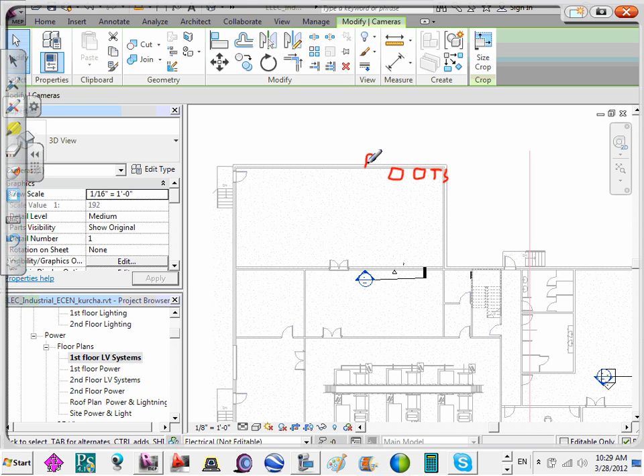Okay, so we got 4 zones. Looks like we're going to have a flow and a tamper per zone, so 4 of each, 1 for each zone. But you're going to have more for zone 2 here, which is the computer room pre-action panel. And that is a dry pipe system, so you're going to monitor high and low air on it as well.